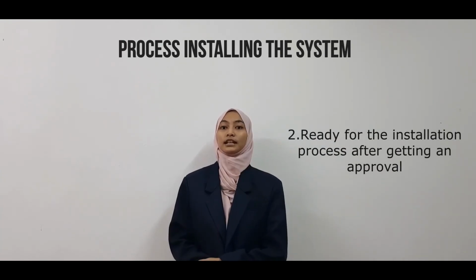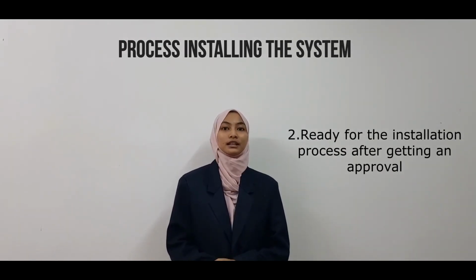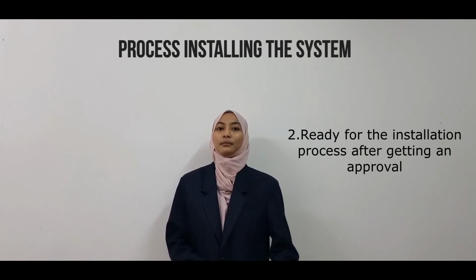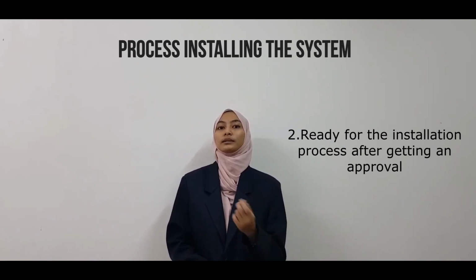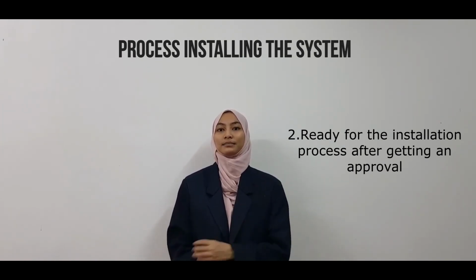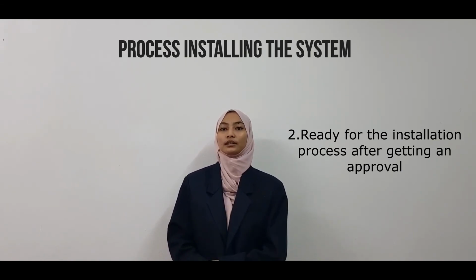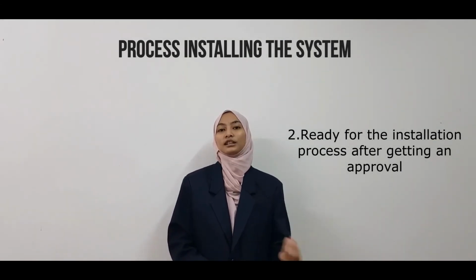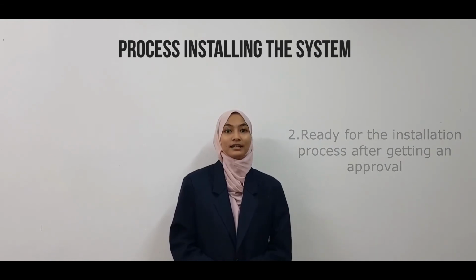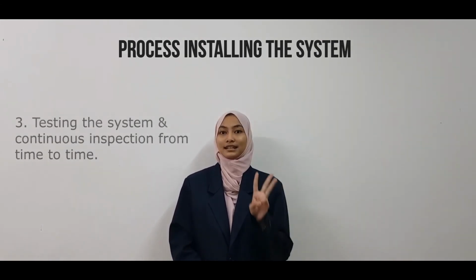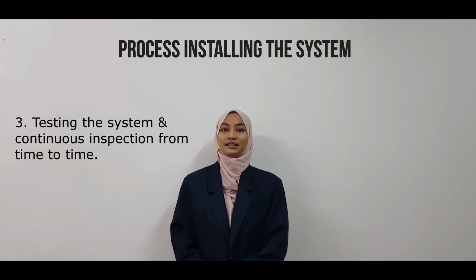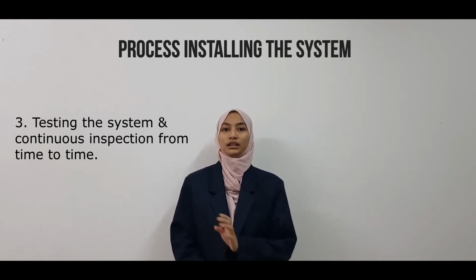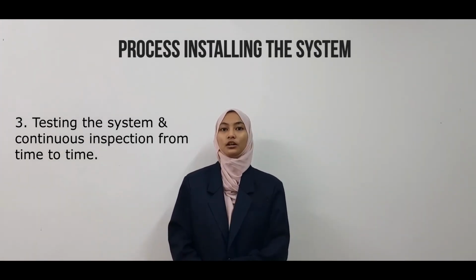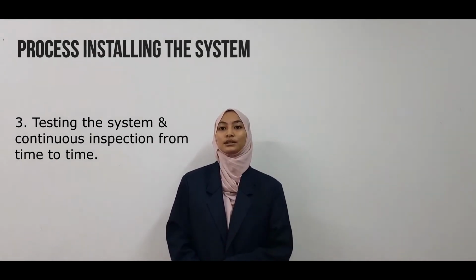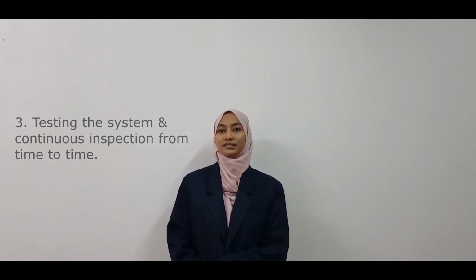Secondly, after getting approval from the local fire safety authority, it is ready for the installation process. By referring to the drawing, the contractor on the project must guide his team on the steps and processes to properly install the fire sprinkler system. This installation is commonly done by the pipe fitters at the construction site. And lastly, once the system is completed, it can be tested to make sure everything is working as designed. Once the system is installed and operable, the building owners must then do continuous testing and inspection of the system depending on the building and occupancy type.